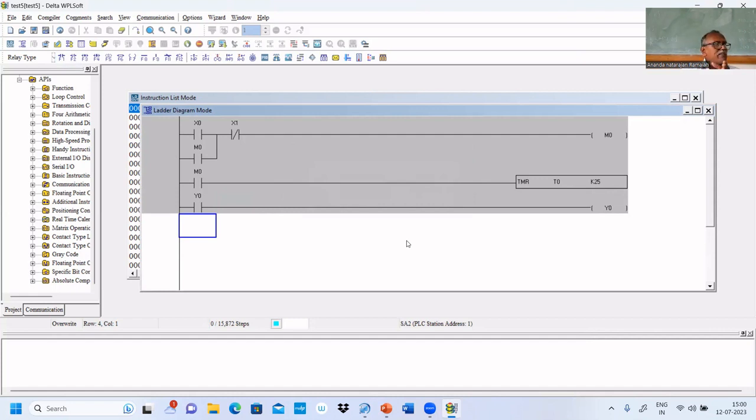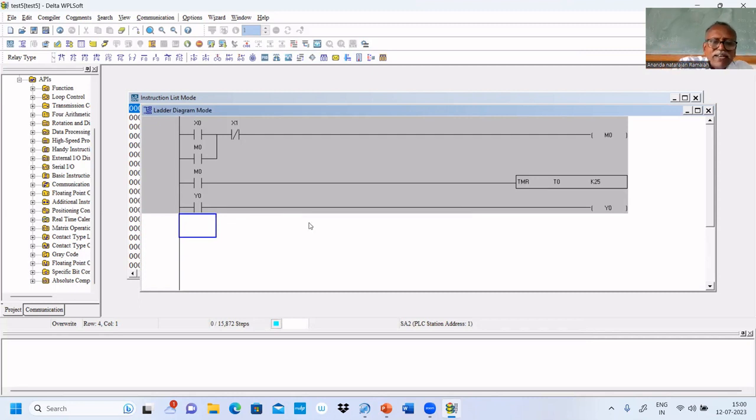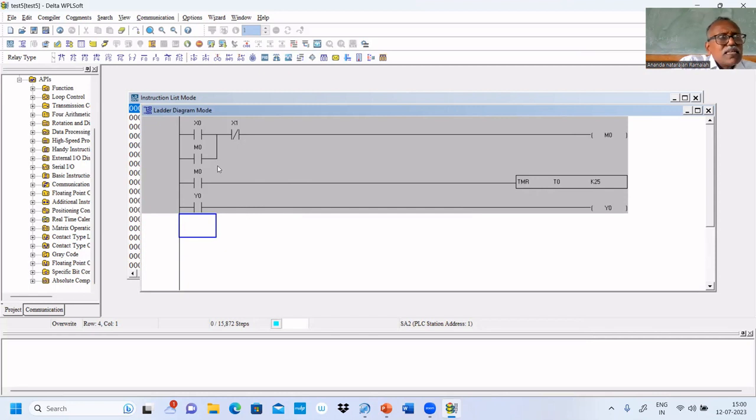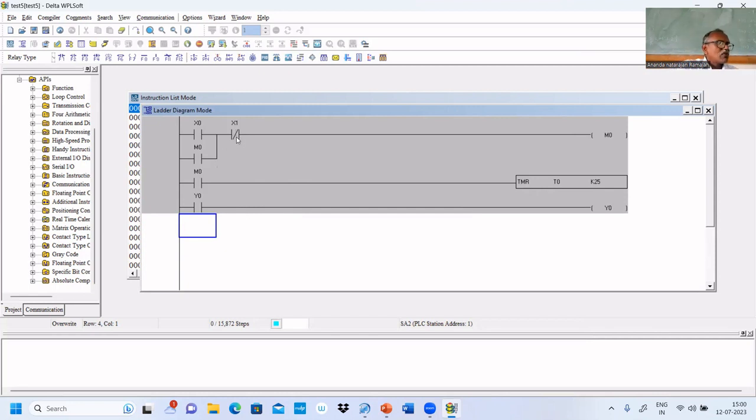If you press X1 immediately, M0 becomes 0. As M0 becomes 0, timer output also becomes 0. That's why immediately it will be turned off. It works fine. The sealing contact, we have to check. Because of X1 in series, sealing contact also will go off. No problem, that problem will not come here.